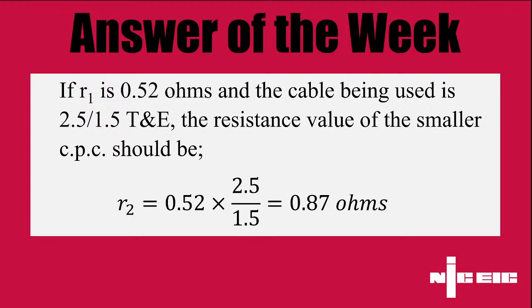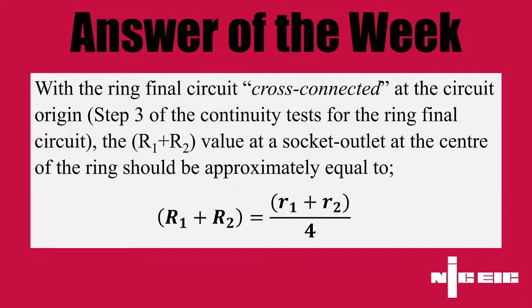Then we've got to look at doing step 3 of your continuity test, your R1 plus R2 test. It's what we generally call the figure of 8 test, what most electricians do out in the real world. So you're crossing over the line of your incoming cable and the CPC of your outgoing cable, crossing those two legs over, and you do the same for the outgoing line and the incoming CPC. And then to do the maths to work out what the intended value is in the middle of that ring, you take the sum of your R1 and R2 and divide it by essentially the 4 parallel paths that you now have. So it's R1 plus R2 divided by 4.